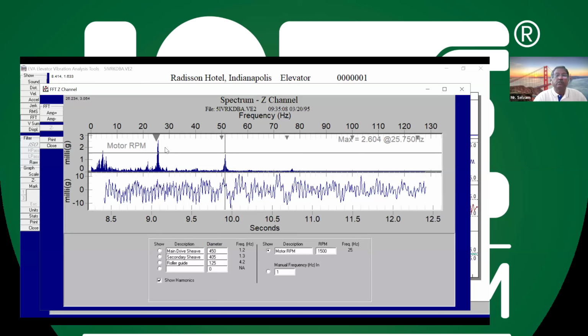So this particular item is rotating at 25 hertz. Any rotating element, its revolutions per second is called its frequency. For example, you have a 200 rpm gearless motor, 200 revolutions per minute, which per second means maybe 2.5 or 3 revolutions per second. It's 3 hertz basically. So a gearless PMSM motor will be in the order of 3 hertz. There is a calculator here: you can put in the RPM and you get the frequency. For example, a geared motor at 1500 RPM means 25 hertz.